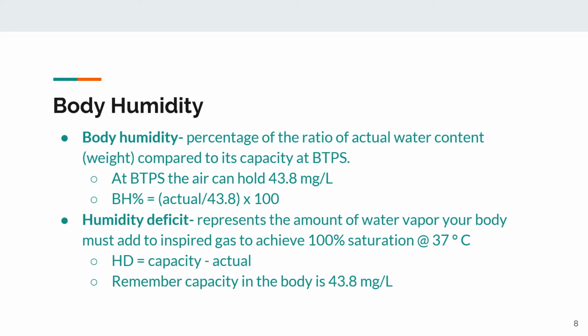Anyway, by the time the air arrives at the distal airways, or the far airways, it needs to be warmed to about 37 degrees. So we're able to set that temperature on those heaters, along with how much rain out, or how much moisture it is able to put out on our heated circuits. And then we would like it to be fully saturated with water. Of course, you have to be careful not to go to the other extreme where you have a lot of extra water in your circuit, and people are getting inadvertently lavaged by all the water that's in the tubing. So you have to find a balance.